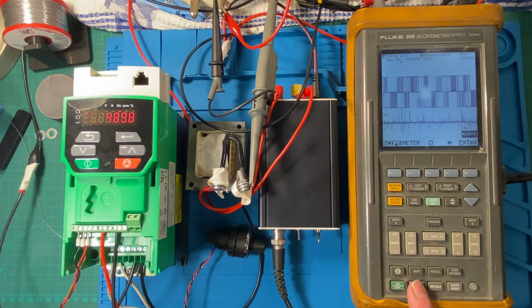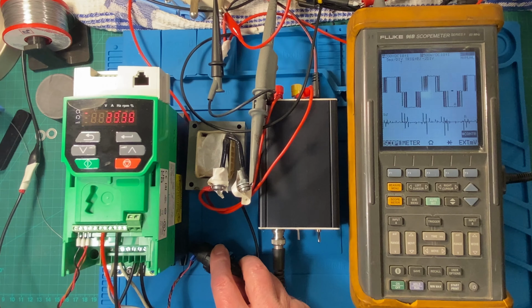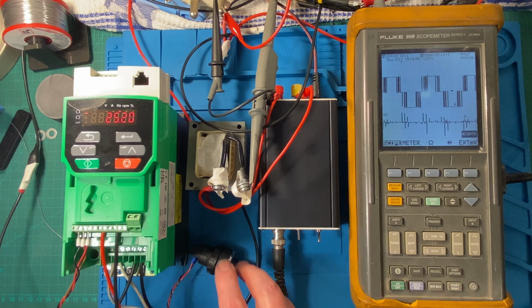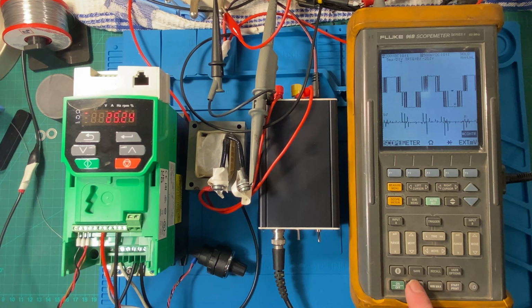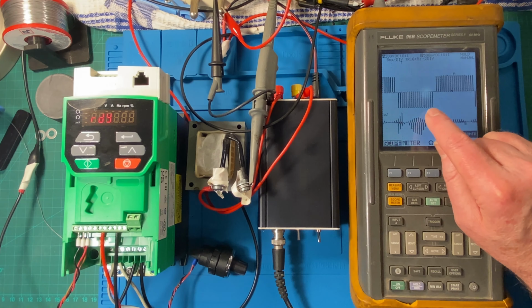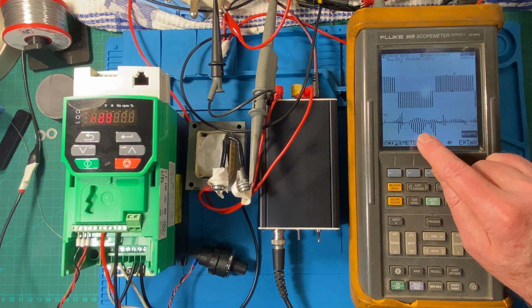So if I fire it up and turn the frequency down to halfway, 25 Hertz, and we capture that, it looks like that. So that is now basically your reduced voltage. You can see the pulses start off narrower, get wider, and then go narrower again. And there you can see the effect on the current.